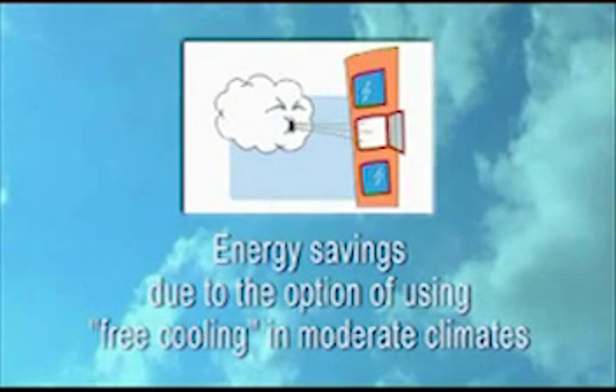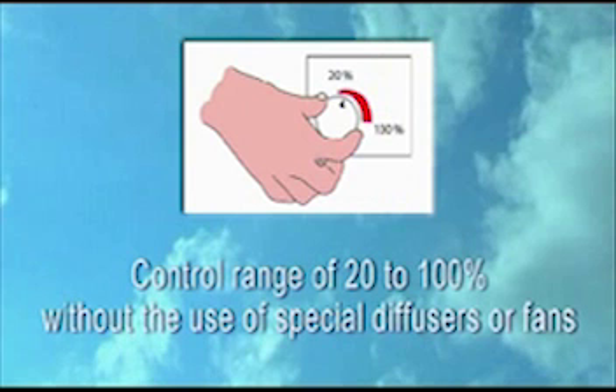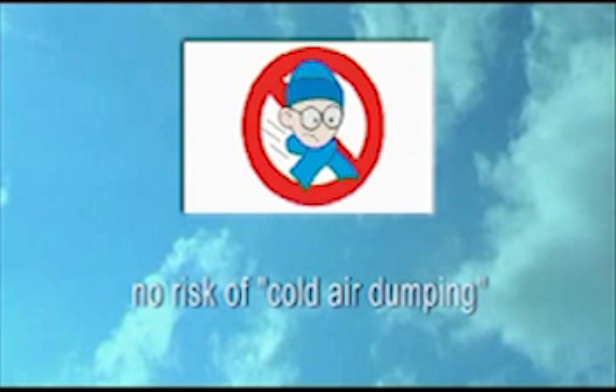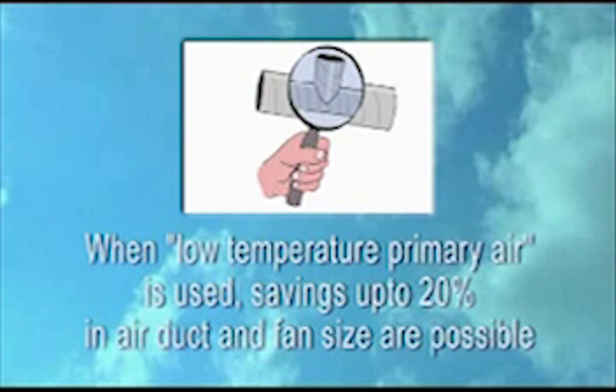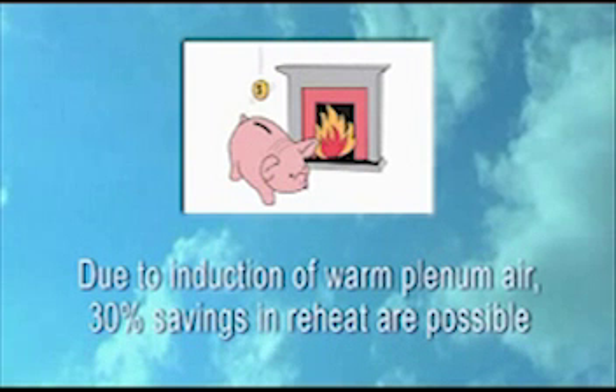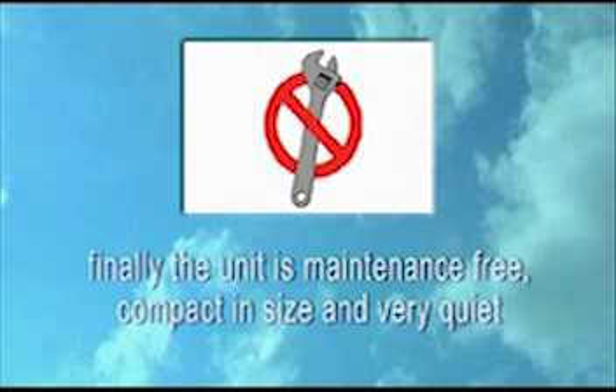Besides improving the indoor climate and human thermal comfort, the induction VAV system has more benefits. Energy savings due to the possibility of using free cooling in moderate climates. Control range of 20 to 100% without the use of special diffusers or fans. No risk of cold air dumping. When low-temperature primary air is used, savings of up to 20% in air duct and fan size are possible. Due to induction of warm plenum air, 30% savings in reheat are possible. Finally, the unit is maintenance-free, compact in size, and very quiet.